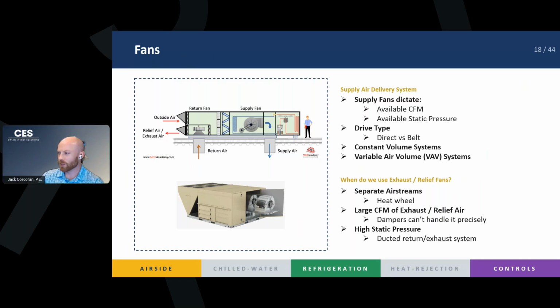Oftentimes, in smaller systems, this is not required. Your supply fan has enough static pressure to pull your return air back into the building, and your dampers just modulate open and close to allow the CFM. But sometimes you want to keep those airstreams separate. When you have energy recovery heat wheels, you need a separate fan, because the airstreams don't really touch each other, so you're going to need two fans. You need a way to push the supply air and pull the exhaust air out of the building.